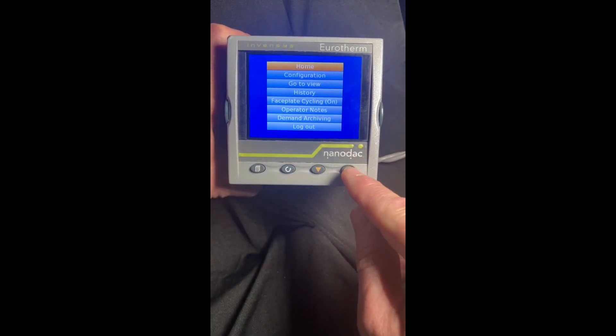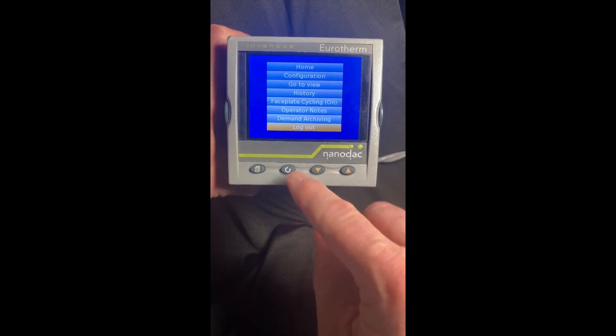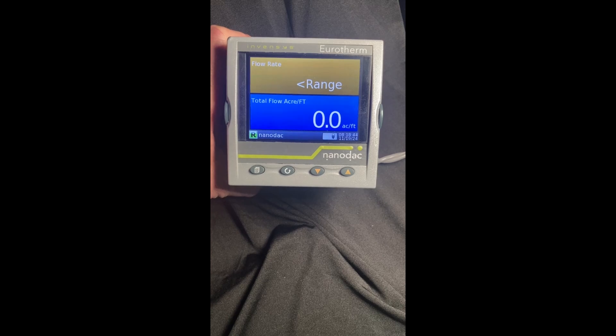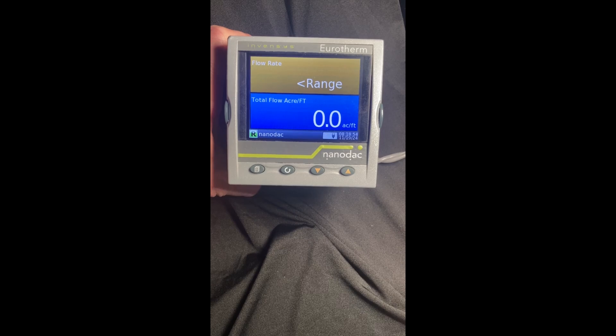Again, in this case we're in configuration mode, so we want to make sure we log out or else the controller is not going to control the process. We can avoid this by setting up a supervisor level — in the supervisor level you can do the demand archive but the controller will continue to control the process.